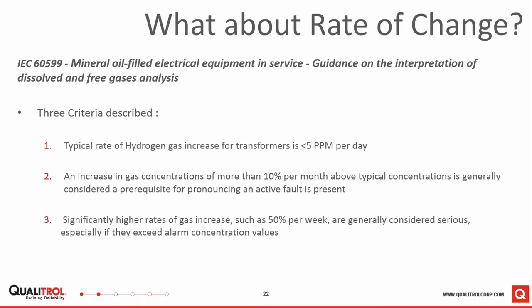So if you see a 10% increase of concentration relative to what you had, then it's likely to be because of an active fault. And significantly higher rates of gas increase, such as 50% per week, are generally considered serious, especially if they exceed alarm concentration values. And we've just seen alarm concentration values. So the guidelines are quite broad, but nonetheless, they provide you with a quick and easy mechanism to make decisions on what action you might take.